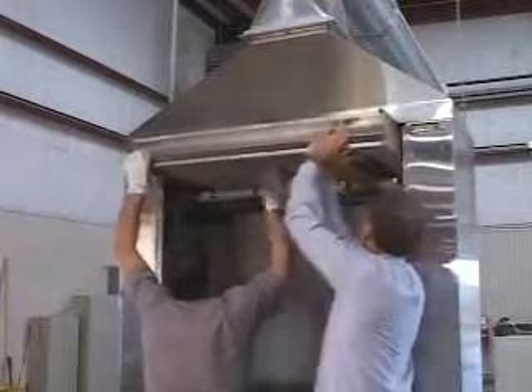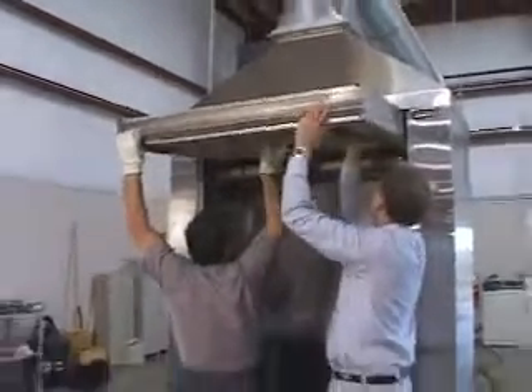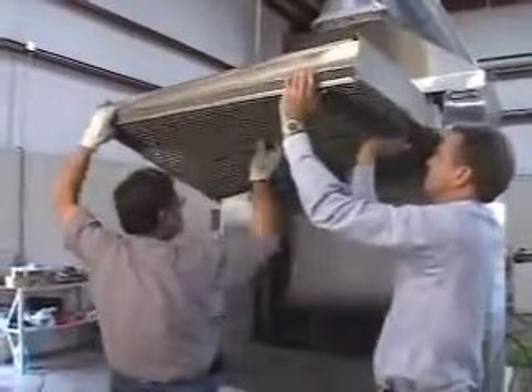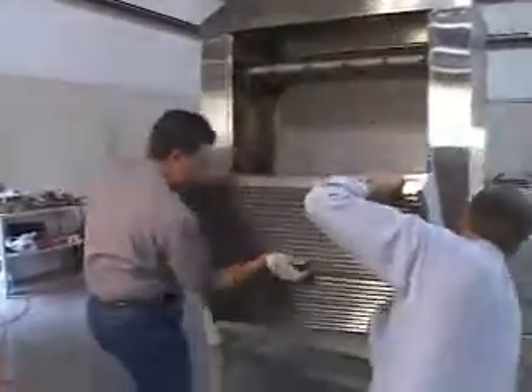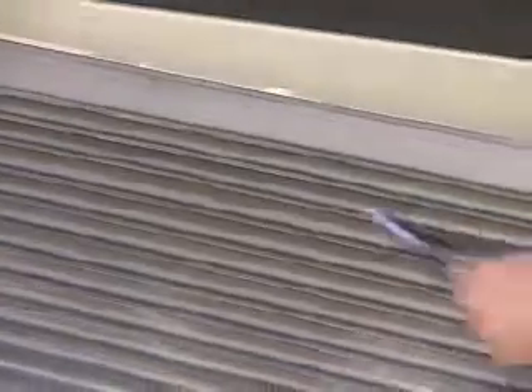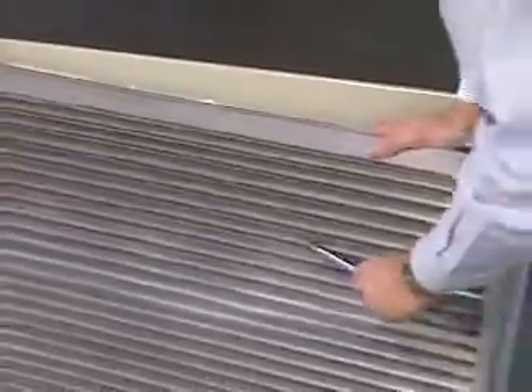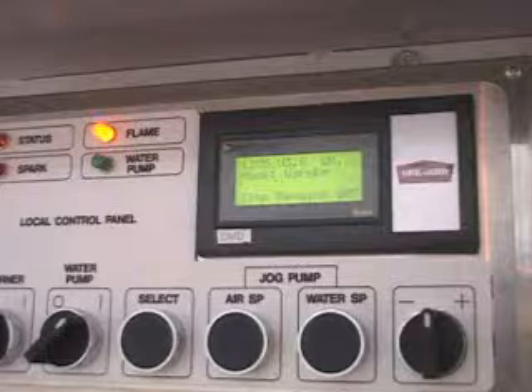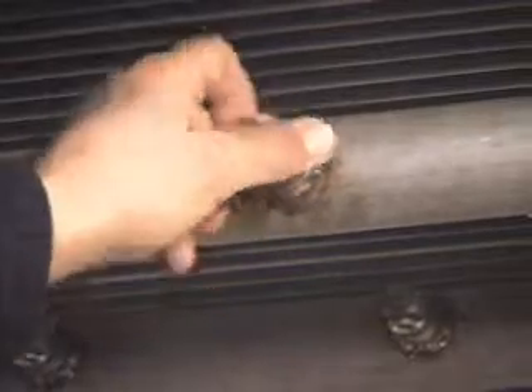Inspect the mist eliminator by pulling it out and looking at both sides. If minor buildup has occurred, scrape out the lint or scale with a screwdriver or similar tool. If there is a lot of buildup, replace the mist eliminator. Using the jog button for the water pump, make sure that the spray is coming from all 24 spray nozzles. A flashlight is useful to carefully observe the spray while a second person presses the jog pump button. If a nozzle needs cleaning, unscrew it from the pipe and use a small screwdriver to remove the contaminant.